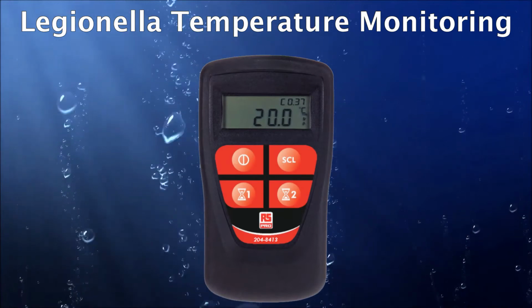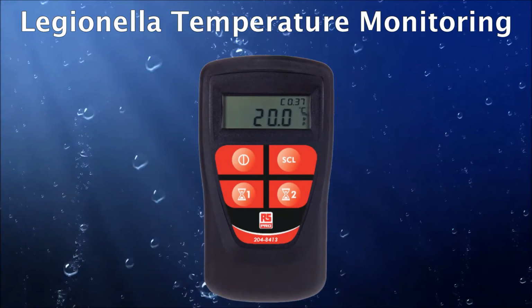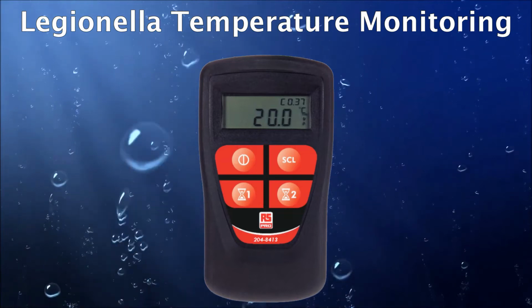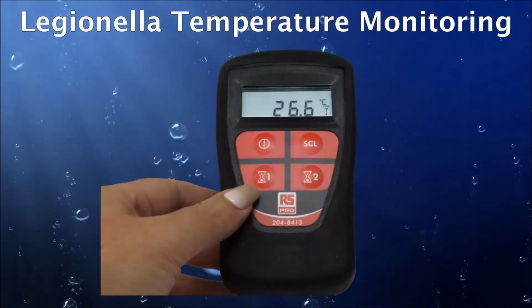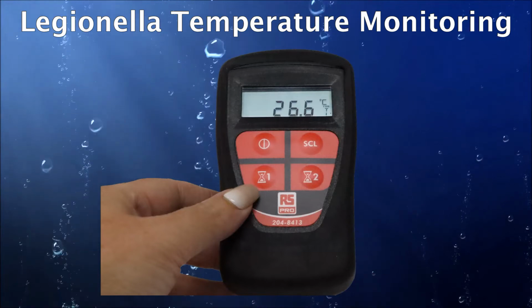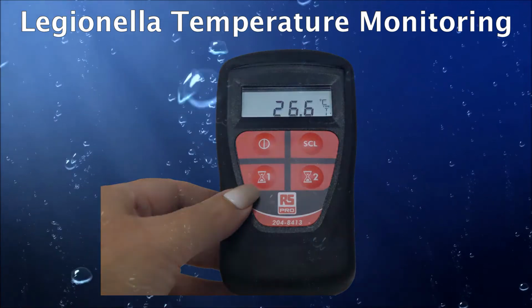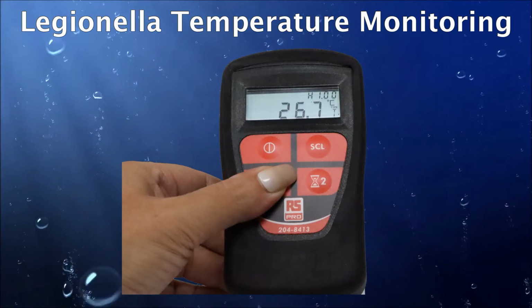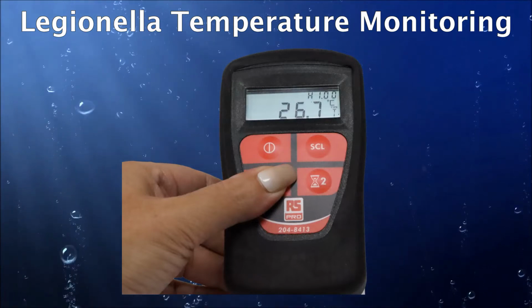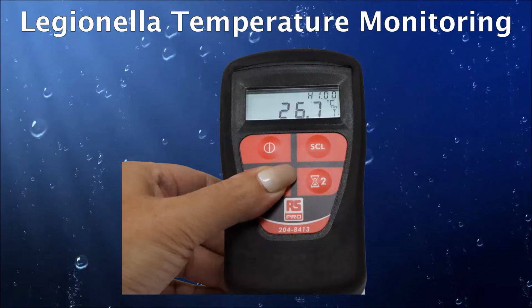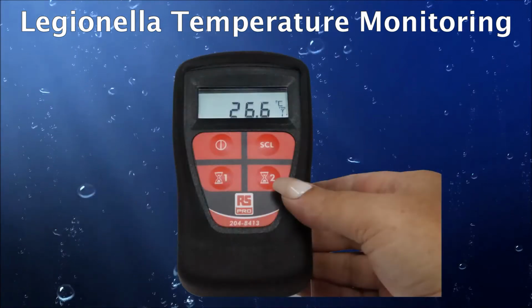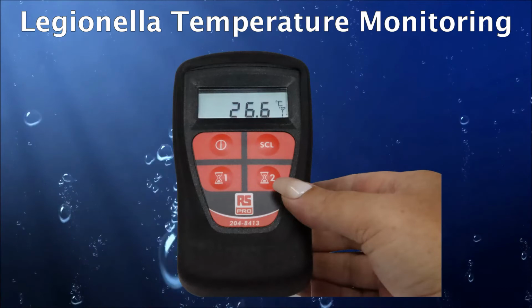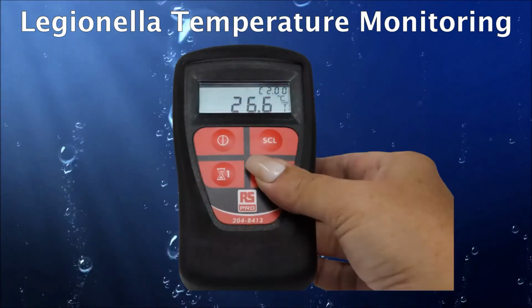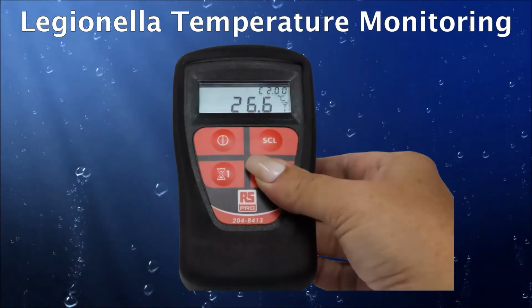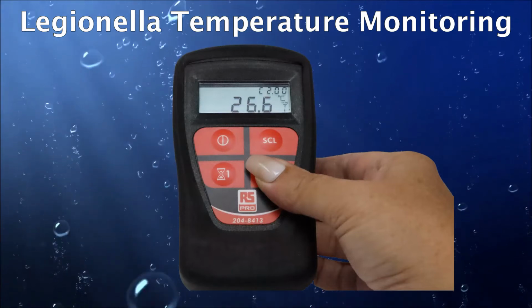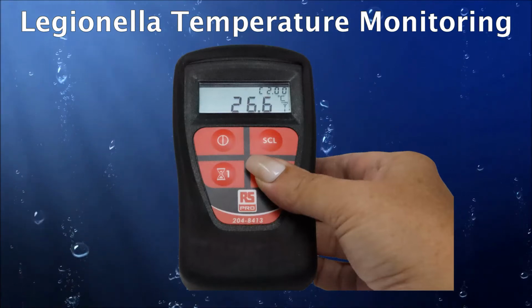Using the integral timer. When performing a running water or immersion temperature test, the timer buttons on the handheld's keypad will come into their own. The 1 timer button is for the 1 minute hot water countdown. Press this and the display will show H1.00. It will automatically start counting down. Press that button again and the timer will disappear. The 2 timer button is for the 2 minute cold water countdown. Press this and the display will show C2.00, and again the automatic countdown will start. Press once more and the timer will disappear.